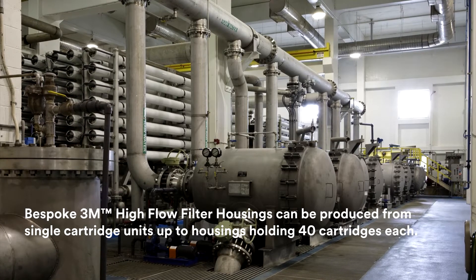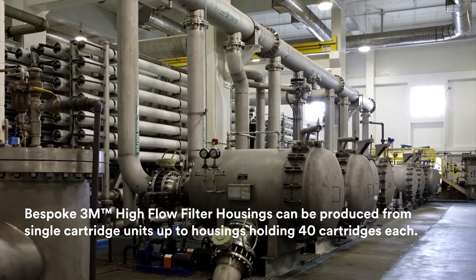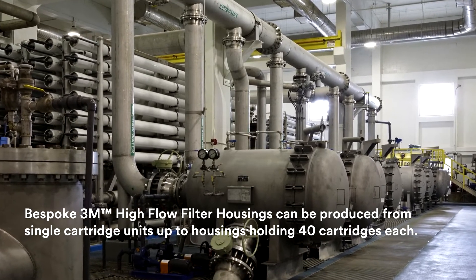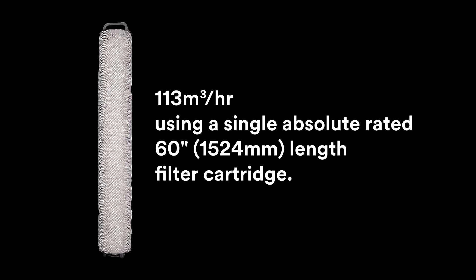Ideally suited for high flow rate applications such as pre-RO membrane protection and beverage bottling plants. The systems utilize large 6.5-inch outer diameter compound radial pleated cartridges, which accommodate flow rates of up to 113 metres cubed per hour per filter.